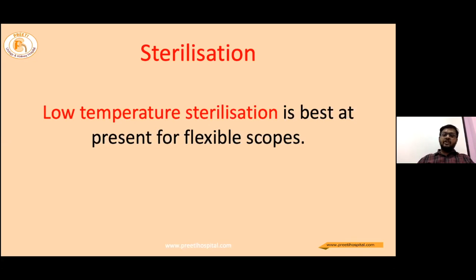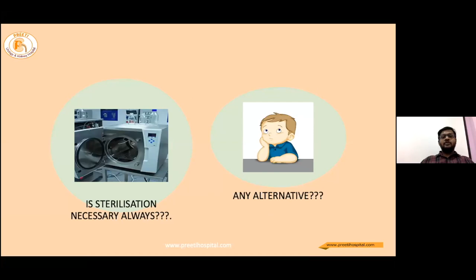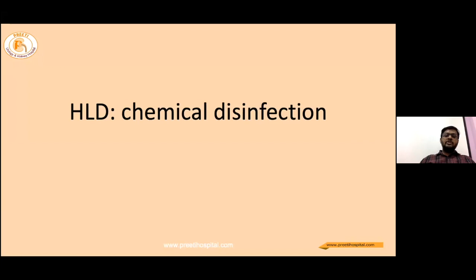For sterilization of flexible scopes, low temperature sterilization is best at present. Is sterilization always necessary, or is it possible to sterilize after every case? No. Are there any alternatives? Yes, there is one alternative called high-level disinfection. What is this high-level disinfection? Nothing but a chemical disinfection. Though it's a disinfection, given adequate time, these chemicals can act as a sterilization also.